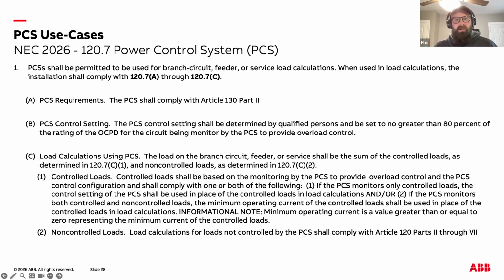The code then outlines two different methods for performing load calculations, depending on what the PCS is monitoring and controlling. If the PCS monitors only the controlled loads, then the PCS control setting replaces those loads in the calculation. If the PCS monitors both controlled and non-controlled loads, then the calculation must use the minimum operating current of the controlled loads instead of their full nameplate values.